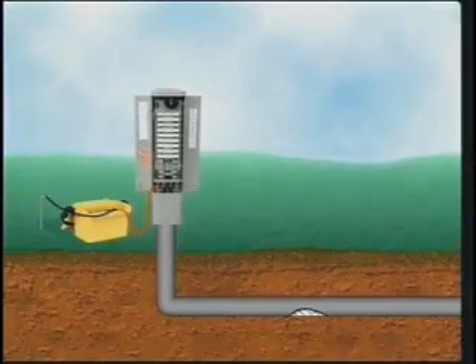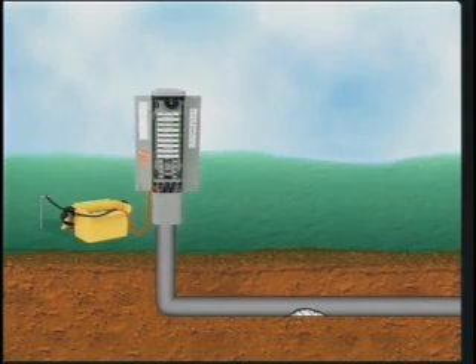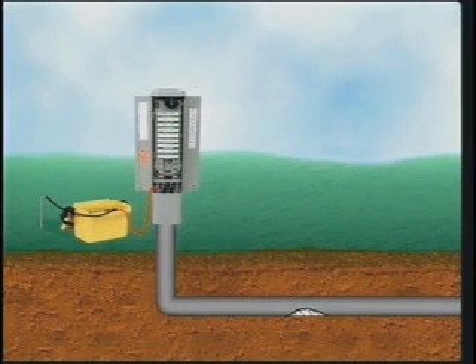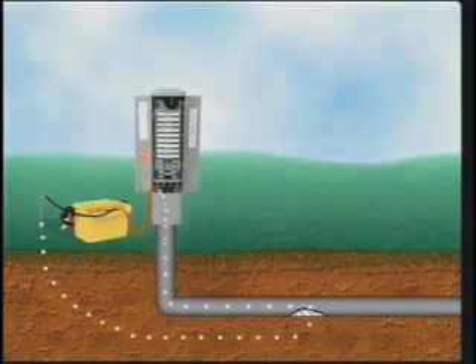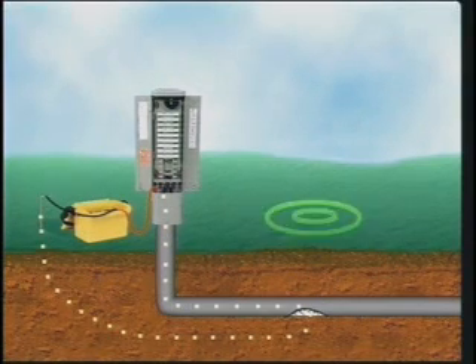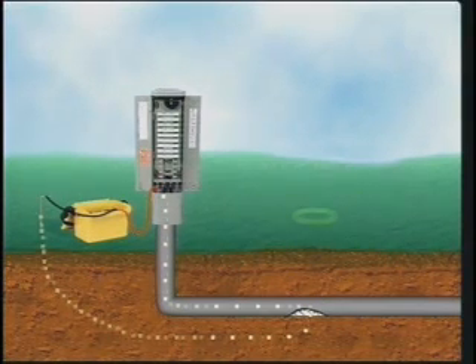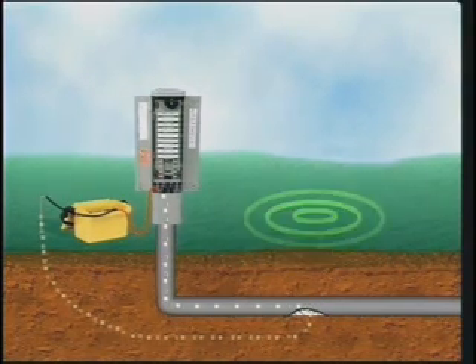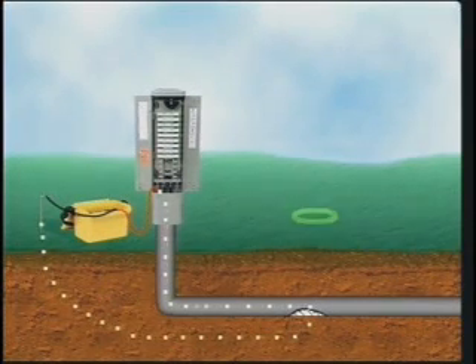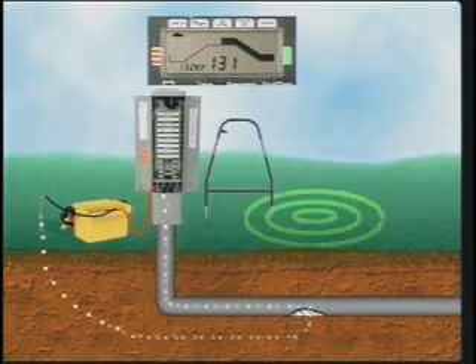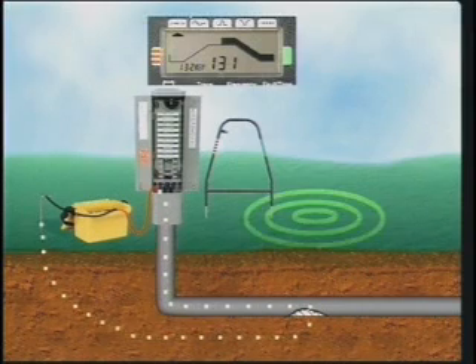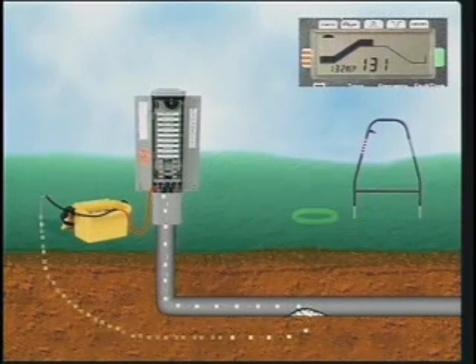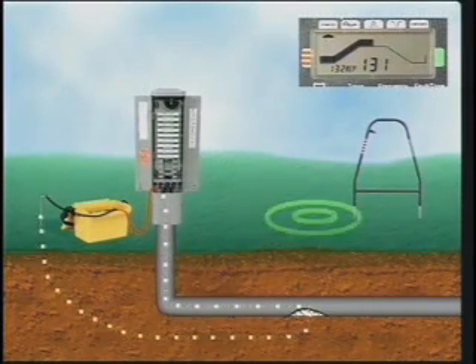To locate a buried fault, use the direct connect method to apply the fault locate signal to the cable sheath. At the fault, most of the current stops traveling through the cable and travels through the earth. This causes a voltage gradient around the fault that can be detected at the surface. Using the earth contact frame, the receiver not only detects the voltage gradient, it also indicates the direction to the gradient.